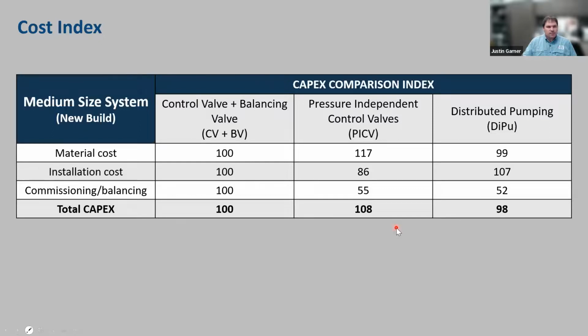I would say that these figures, depending upon the system, might be a little on the low end, but certainly, in certain instances, the 55, 52 order of magnitude with respect to a traditional system may be accurate. I would say most systems, especially if you were going to blend heating water and chilled water together, it's probably going to still be a little bit higher than this, although there will be a cost savings in most cases, especially with respect to the balancing piece.